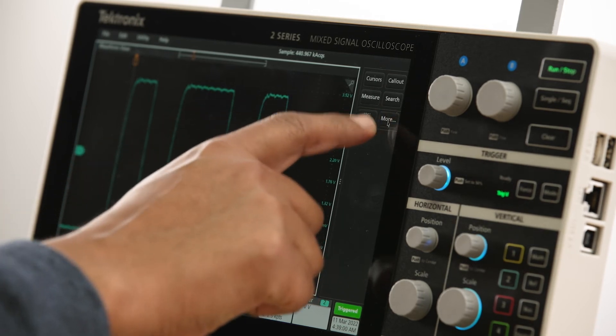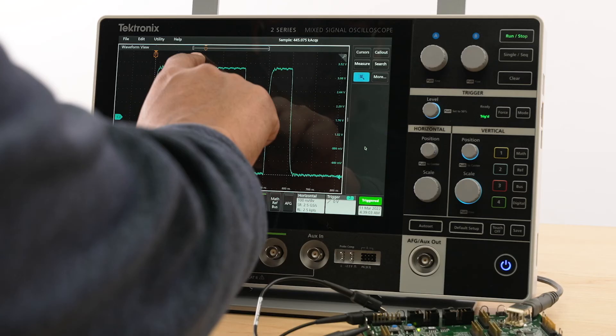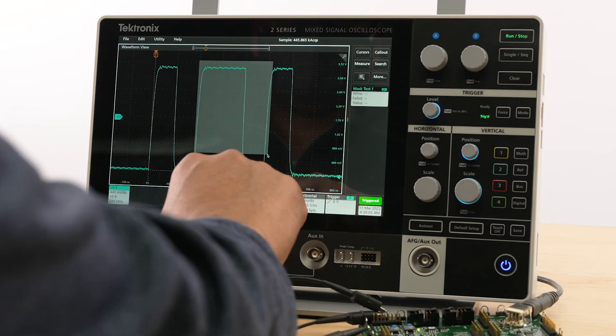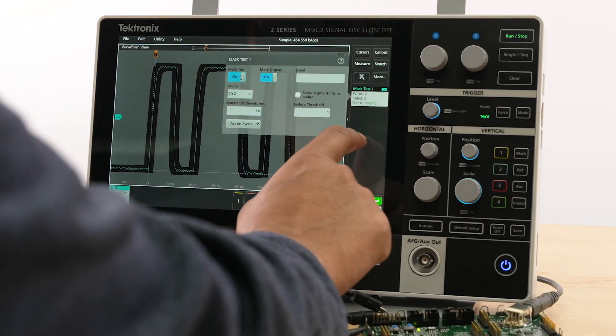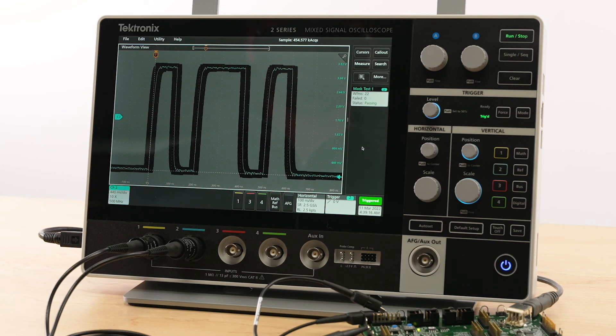You can also perform various actions like save data, stop acquisition, or trigger on other external instruments. Mask testing offers a quick and easy way to check the quality of a signal in production facilities or in testing the quality of a signal to a standard. The 2 Series MSO has both limit mask and eye mask capability to perform these tasks.